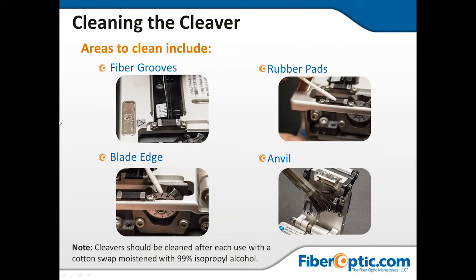Areas to clean include, and it's very important that you take some time to do this: on the top left, fiber grooves. You have 2 grooves, one for 900 micron, the other one for 250/125. I like to take a piece of just bare fiber and run it through the grooves. You can then take an alcohol wipe and just run it through.